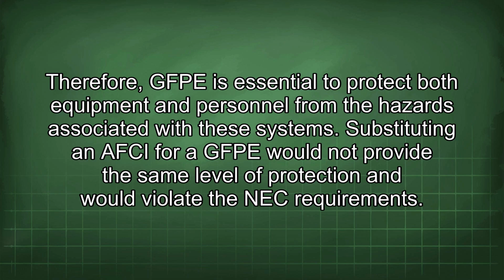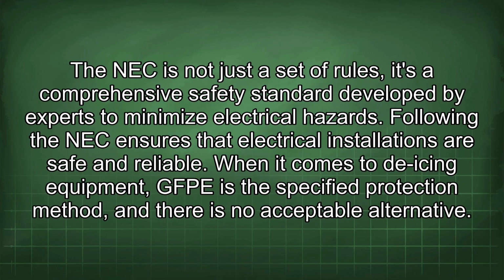Substituting an AFCI for a GFPE would not provide the same level of protection and would violate the NEC requirement. The NEC is not just a set of rules, it's a comprehensive safety standard developed by experts to minimize electrical hazards. Following the NEC ensures that electrical installations are safe and reliable. When it comes to de-icing equipment, GFPE is the specified protection method, and there is no acceptable alternative.